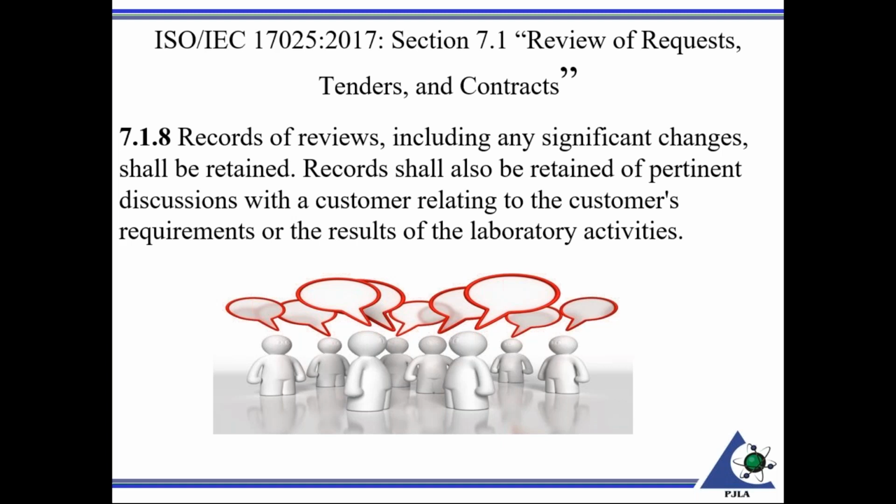Under 718, any record of reviews, including any significant changes, shall be retained. Records shall be retained of pertinent discussions with the customer relating to the customer's requirement or the results of the laboratory activities. So if I'm doing an assessment, for example, I'm looking at perhaps, in my case, a calibration report, and I see the customer can very well should be able to see the record.